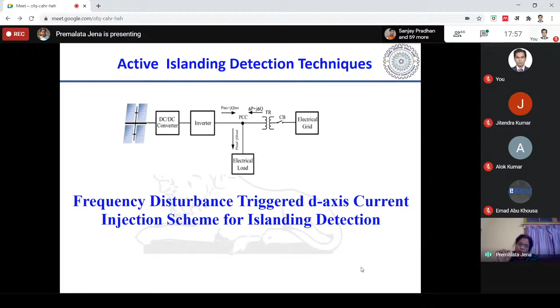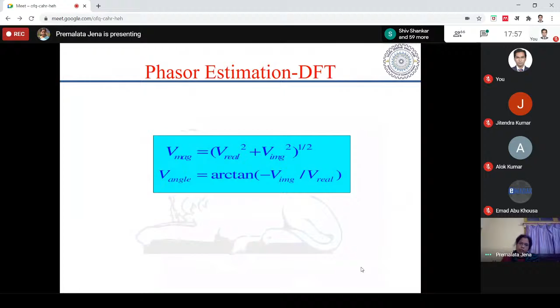To overcome that, we have kept one guard, delta F. What we did was measure the frequency of the grid, FG, as well as the frequency of the DG, my renewable source. We took the difference, FG minus FDG. If it is greater than some threshold, then I will go on injecting the disturbance; otherwise, not. This technique is very effective, we found.